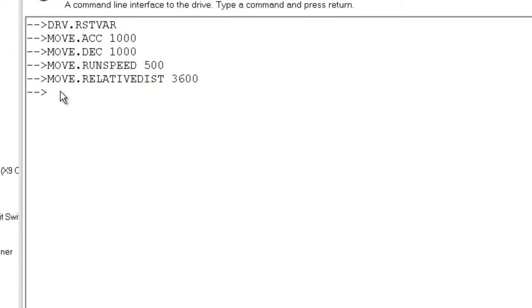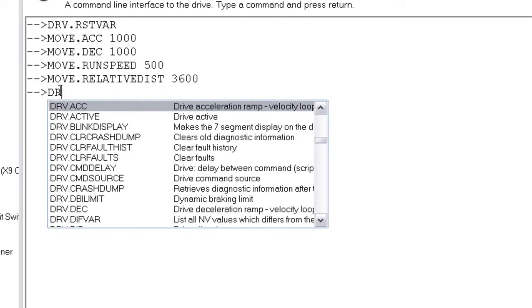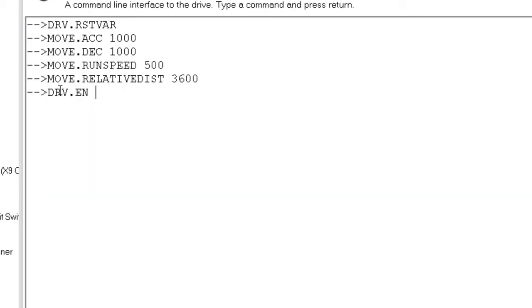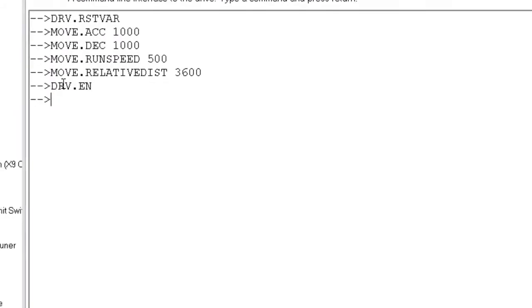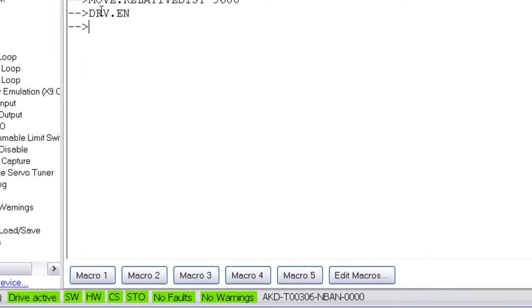To issue the software enable from the terminal, we enter drv.en, enter. Or we can simply click the enable icon on the top of the header. Before we give the move command, we need to make sure the hardware enable is set.